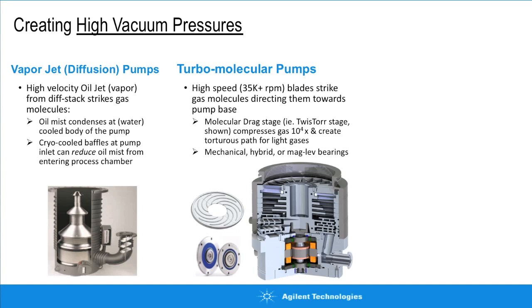A critical component of turbo pumps is the bearing mechanism. Agilent's floating suspension design improves robustness and greatly reduces vibration transmission — particularly important for semiconductor applications and electron microscopes where reducing vibration improves image quality. Some competitors use a hybrid combination of mechanical and permanent magnetic bearings. At the high end, magnetically levitated turbo pumps use electromagnets to float, position, and spin the rotor.